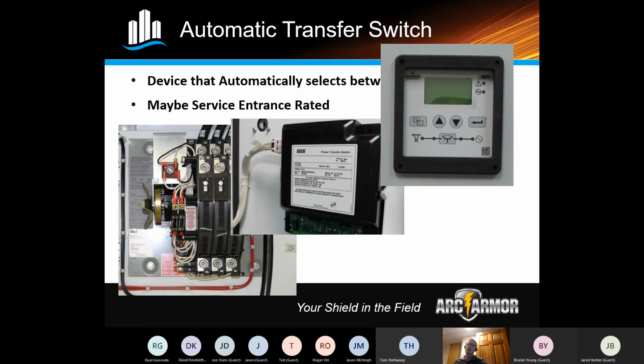So when loss of utility power comes in, the transfer switch will detect that. It will send the signal to the generator. The generator will start. Once the generator is up to speed and can handle the load, it will then transfer the load from the utility power to the generator. And then once the utility power comes back, it's also monitoring that. And once that comes back, it will automatically switch back to utility power and shut the generator off.